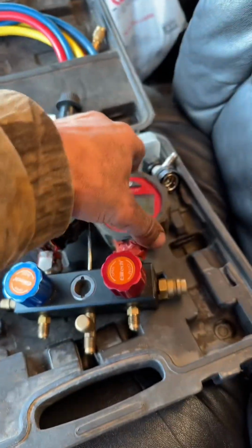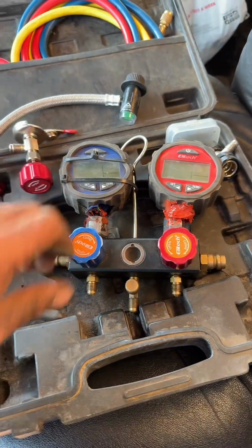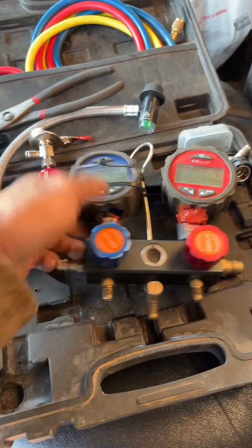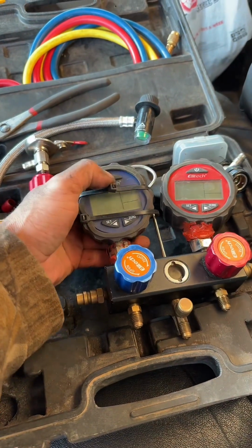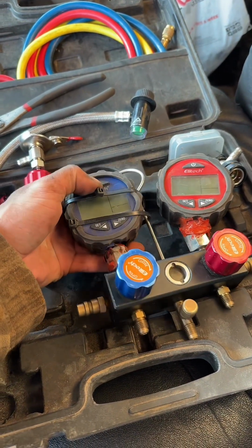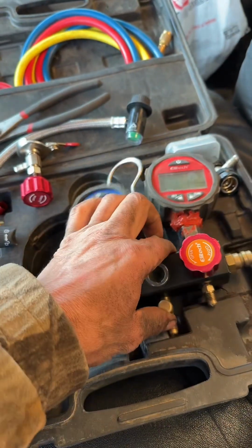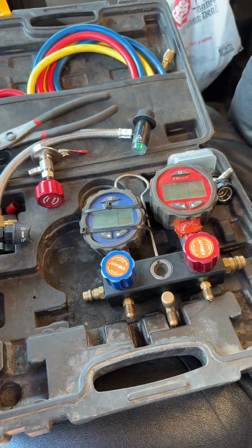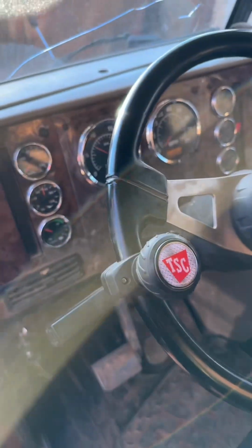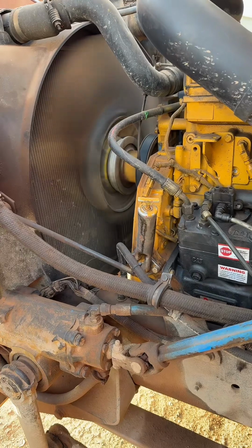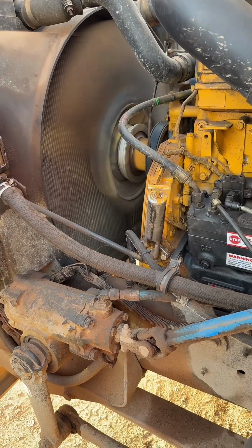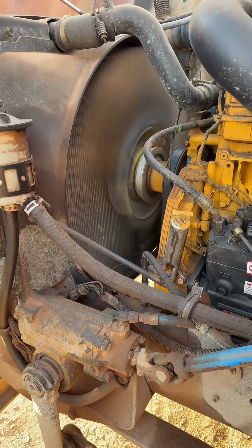Yeah, this is definitely not going to work. Do they even turn on? Yep. So we're going to use an old set of manual gauges because this set will definitely not work. All right, we got the AC on, so let's go have a look. And of course the fan is going to be on because we have no air. Once it builds up air pressure, the fan should shut off.